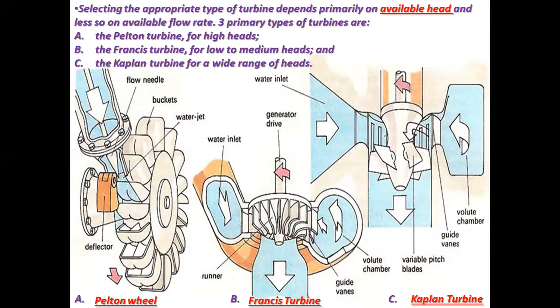Now, selecting the appropriate type of turbine depends primarily on available head and less so on available flow rate. Three primary types of turbines: A, the Pelton turbine for high heads; B, the Francis turbine for low to medium heads; and the Kaplan turbine for a wide range of heads.